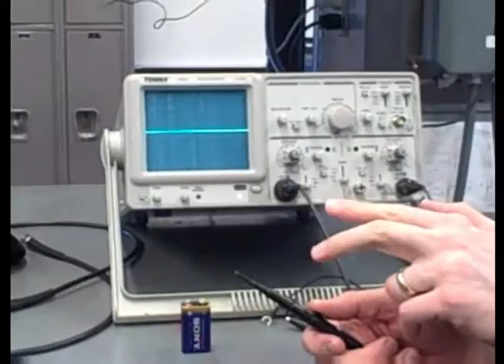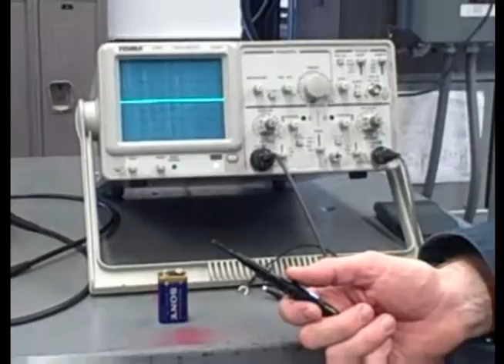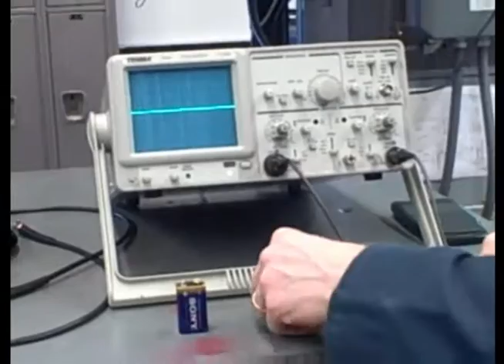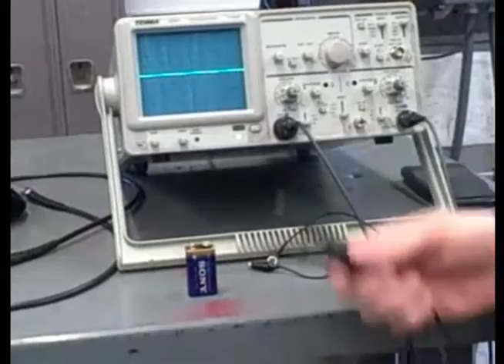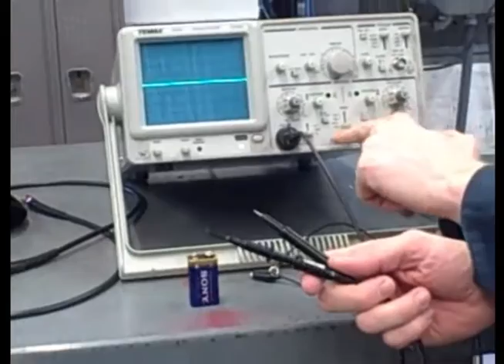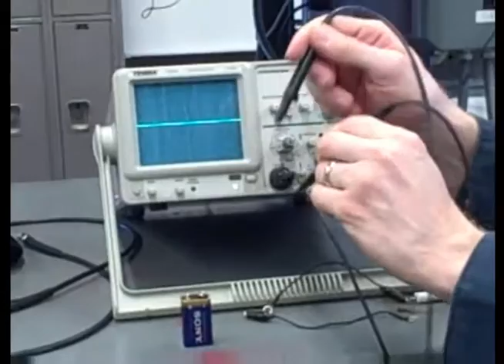If you're looking at a communication network, a two-wire twisted pair, where neither of the wires is grounded, say for example RS-485 or RS-422, where it's a balanced, ungrounded differential signal pair, you do not want to forcibly ground one of those communications lines because you'll cause all kinds of signal reflection problems. So this is what you do. You set up the oscilloscope for dual channel with channel 2 inverted in the add mode, and now you can just go across there like a normal voltmeter without any fear of grounding either one of those communication lines, and now you can measure the signal just fine.